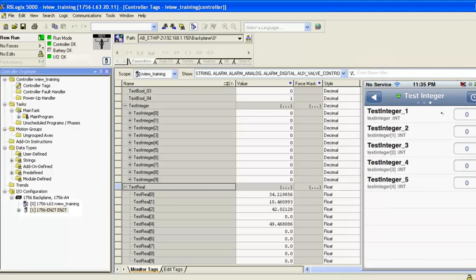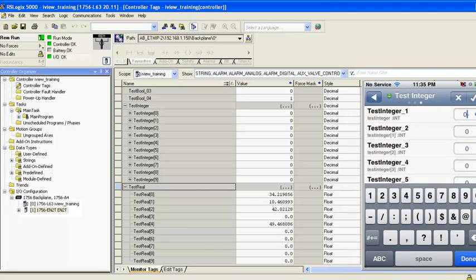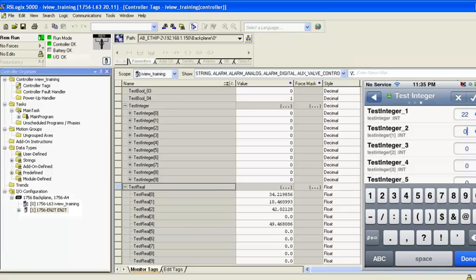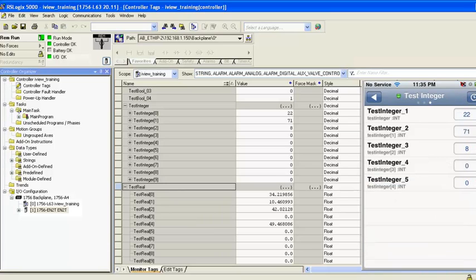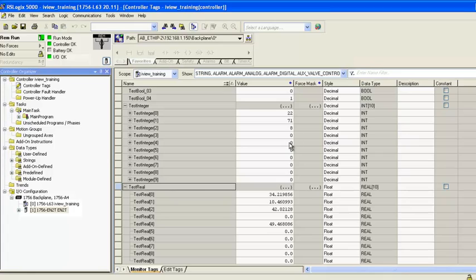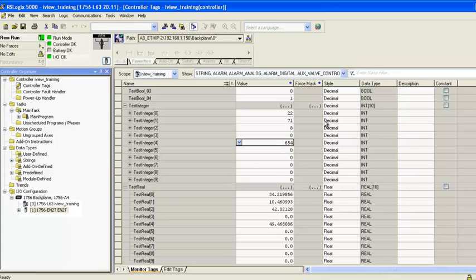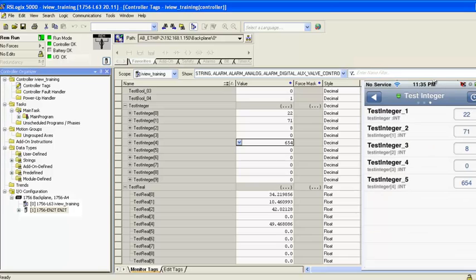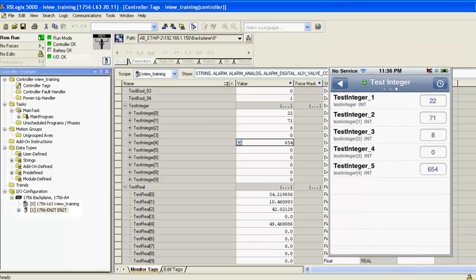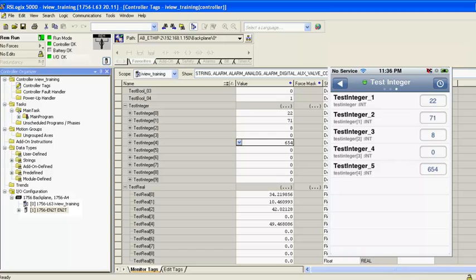If I go to the Integer page and change values in iView, I'll see the tags are also changing in RSLogix. And if I go into the tags in RSLogix and change a value, I'll see it reflect back in iView.